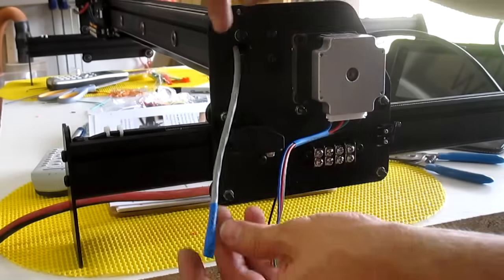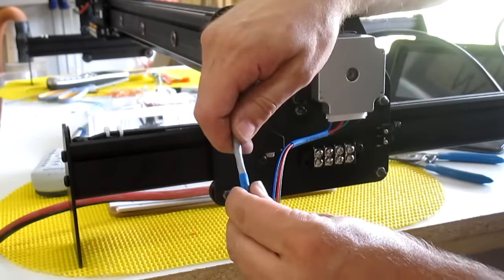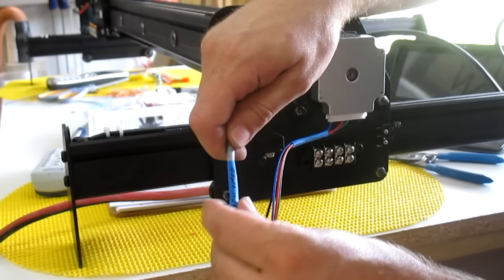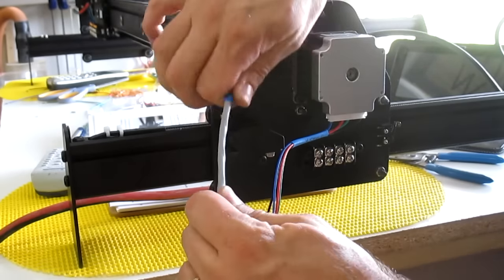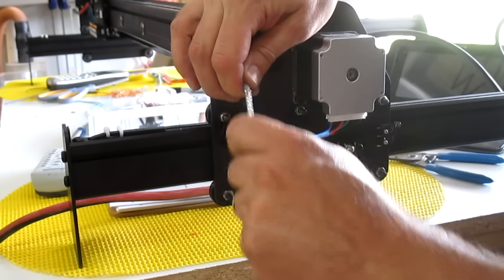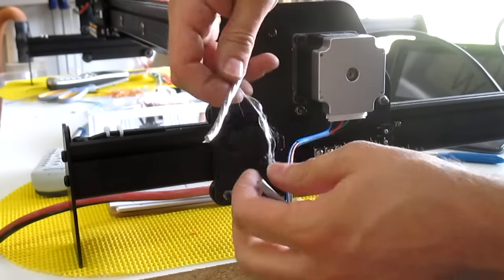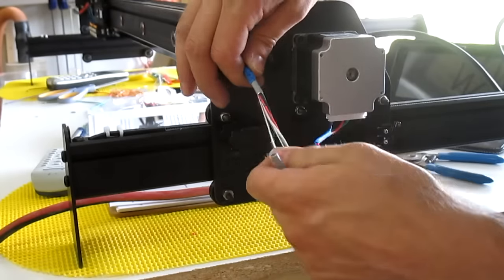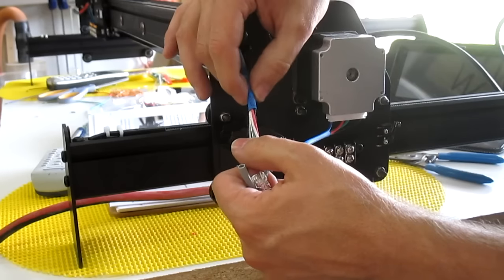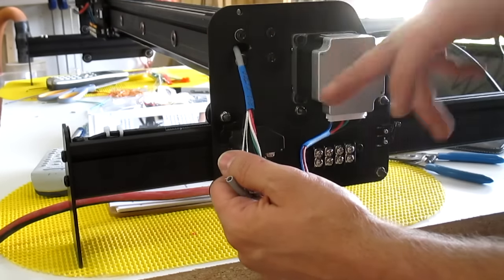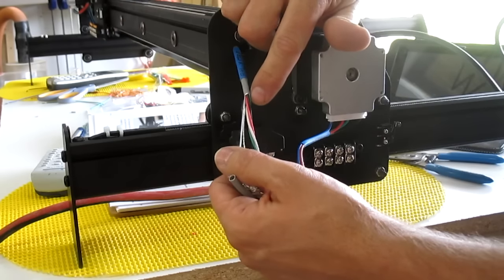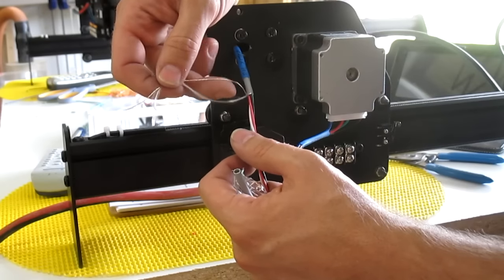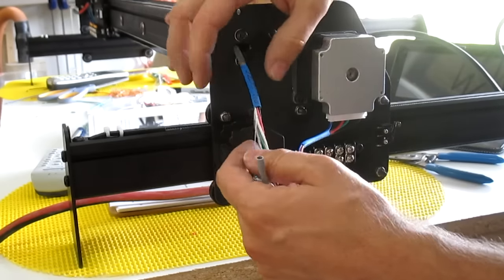Now another little trick I've learned when I'm dealing with wire that has foil shield and actual shield wires in it, I'll put my label, in this case the heat shrink on above where I want to cut it off, and then remove everything. And then I will take the name plate, push it down, maybe this far over, and then heat shrink it. And that way it looks a lot neater rather than having this end showing with a little bit of foil, maybe a little bit of this shield wire sticking out. So this just kind of covers all sins.